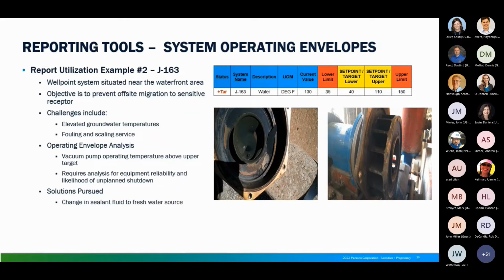On our site, a lot of our well point vacuum pumps are liquid ring style pumps, and they actually use recovered groundwater as the seal fluid. And with that comes a lot of challenges. In particular for 163, since we're dealing with elevated groundwater temperatures, scaling and fouling of the vacuum pumps is a key concern. So we can see from the operating envelopes this particular week, one of the key process data points the technician collects is the exhaust temperature of the vacuum pump. They recorded about 130 degrees.